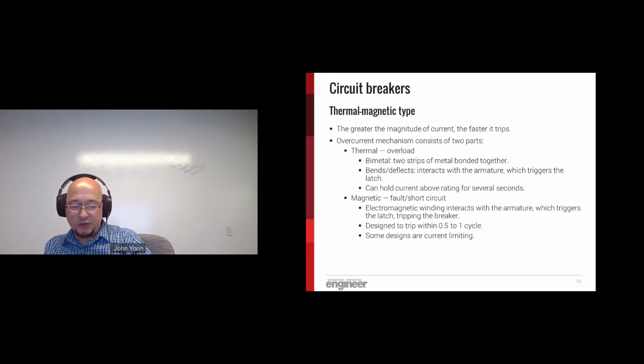The thermal function is accomplished with a bimetal strip. The bimetal strip is two interconnected pieces of metal, and these two pieces of metal have slightly different coefficients of thermal expansion. They will shrink and expand at different rates when heated, like resistive heating when you have current flowing through them. This causes the strip to bend and release a latch to trip the circuit breaker open.